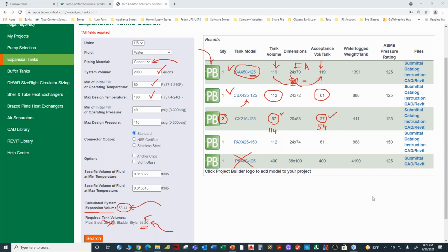Because as the system heats up, you want the temperatures to reflect the greatest amount of expansion. It's okay, by the way, if the expansion tank is slightly larger than what it has to be. It's not going to have any negative effects on the operating characteristics of the system. It's not a good idea to have the expansion tank smaller, because then you have all kinds of problems. The pressure gets too high, the relief valve goes off, and it's not a good day. We don't like that. We don't like not good days.